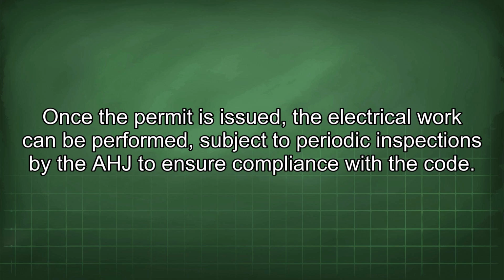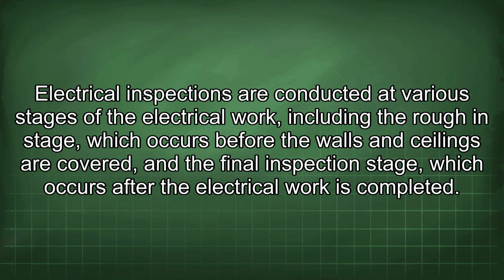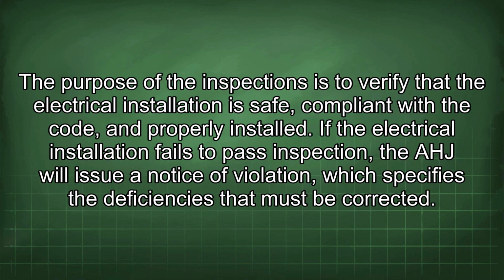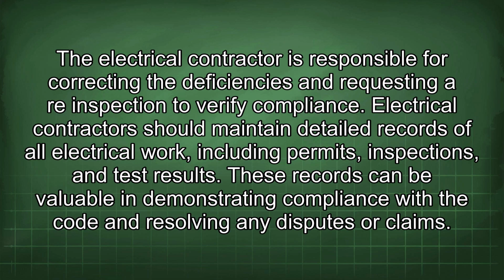Electrical inspections are conducted at various stages of the electrical work, including the rough-in stage, which occurs before the walls and ceilings are covered, and the final inspection stage, which occurs after the electrical work is completed. The purpose of the inspections is to verify that the electrical installation is safe, compliant with the code, and properly installed. If the electrical installation fails to pass inspection, the AHJ will issue a notice of violation, which specifies the deficiencies that must be corrected. The electrical contractor is responsible for correcting the deficiencies and requesting a re-inspection to verify compliance.